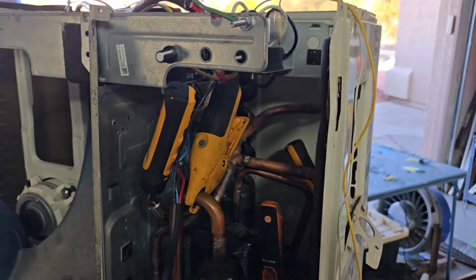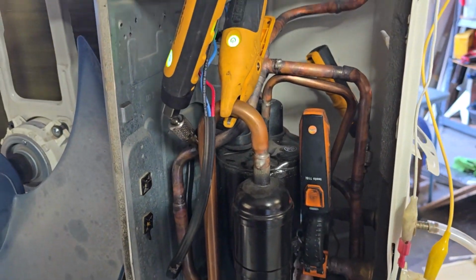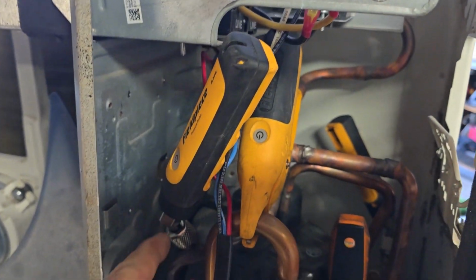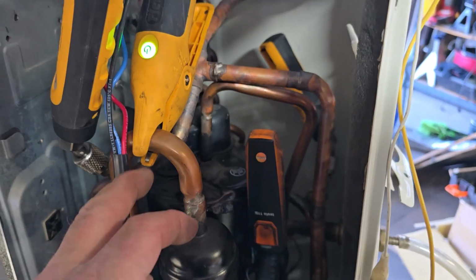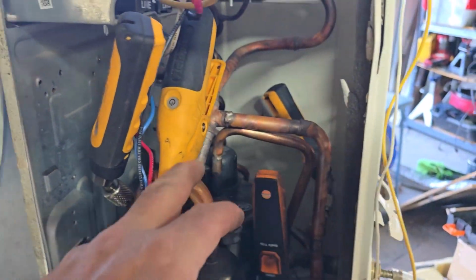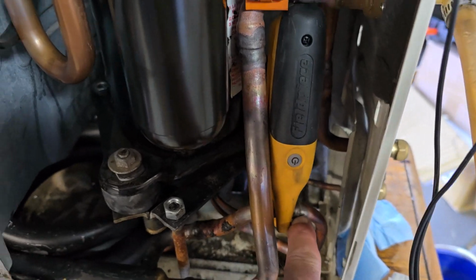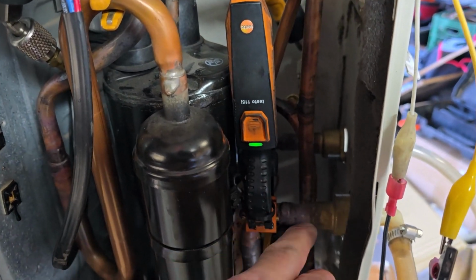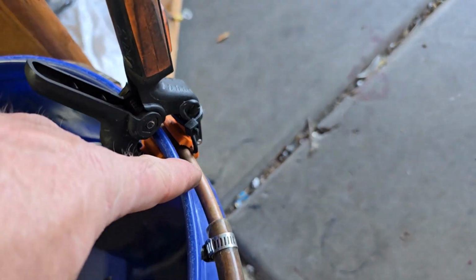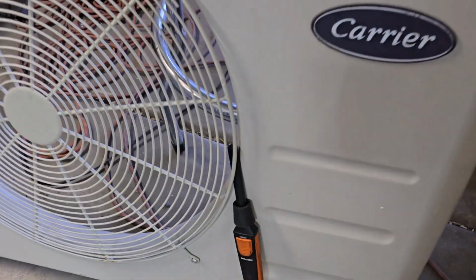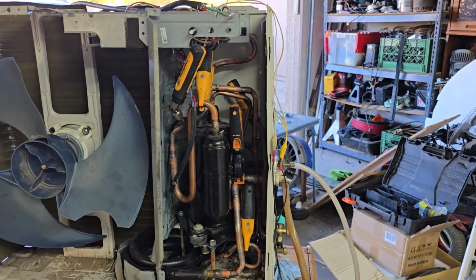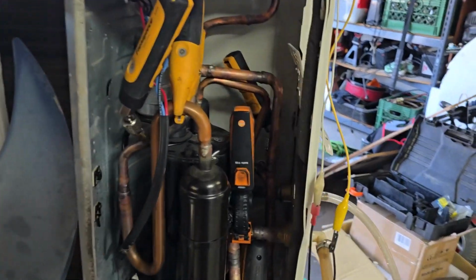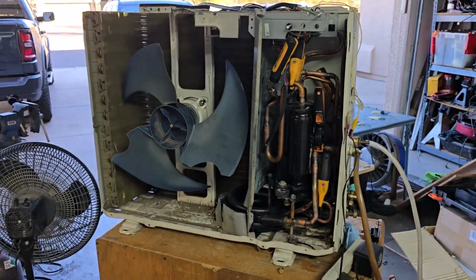I have both the FieldPiece and the Testos hooked up. So I put the FieldPiece on the refrigerant side. We got the suction, discharge over there. And then we got the suction temperature, liquid line temperature right here. And then I've got a Testo probe on the entering water, this Testo probe on the leaving water. Then I have a Testo probe on the entering air and then the leaving air, right there. So I'm going to put this cover back on and we'll start it up. I actually charged it up a little bit ago, pretty close, without taking any readings. So now I'm going to just get the panel in place and give it a little test run.